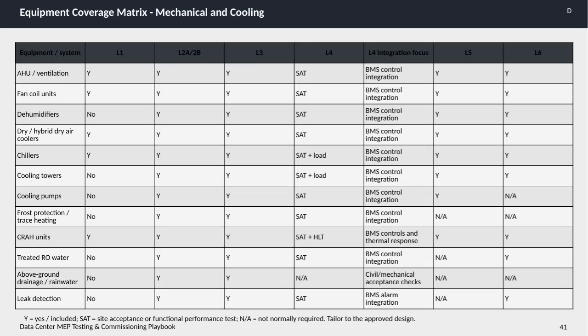Here we have the equipment coverage matrix for mechanical and cooling systems, which outlines the different levels of testing and commissioning required across various equipment types in the data center. Looking at the table, you'll notice columns labeled from L1 through L6, each representing stages or levels of testing, from initial inclusion to system integration and final acceptance tests.